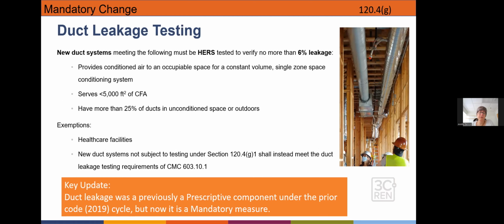Duct leakage is now being triggered sooner. It was previously only a prescriptive component requirement, but now it's been moved to being a mandatory requirement. And when you have a conditioned floor area of less than 5,000 square feet, that duct testing needs to be no more than 6% leakage and must be done by a HERS rater. So that's a little bit more of a requirement you might see when it comes to collecting the applicable forms - you're going to have other forms that might be done by a HERS rater, or it might need to be done by an acceptance test technician.